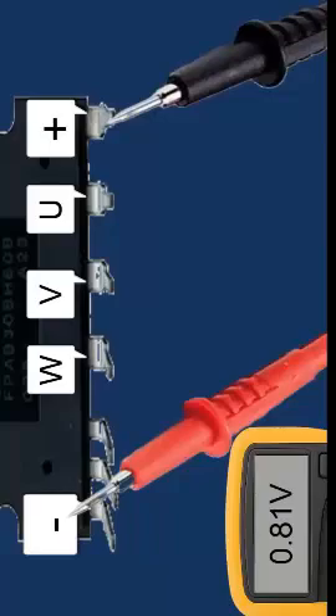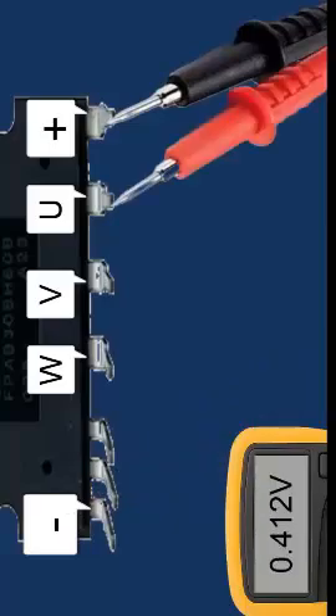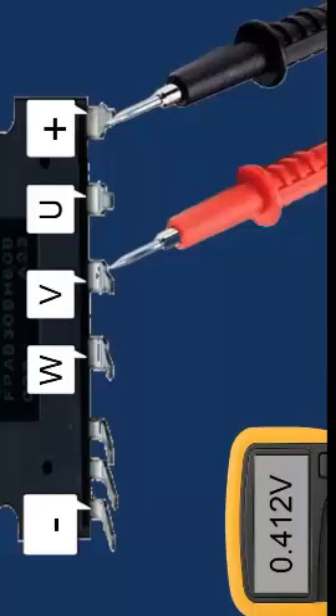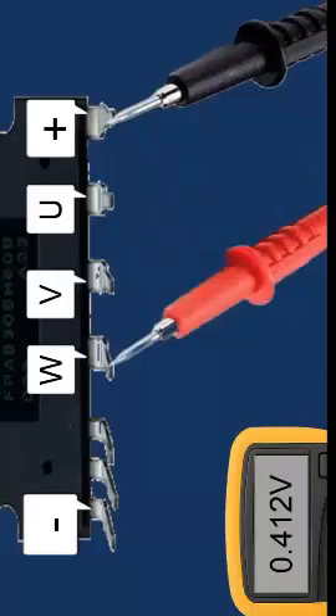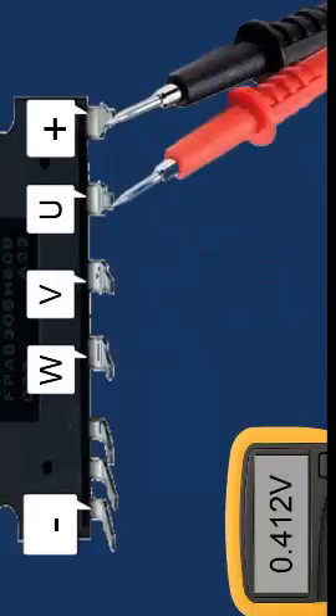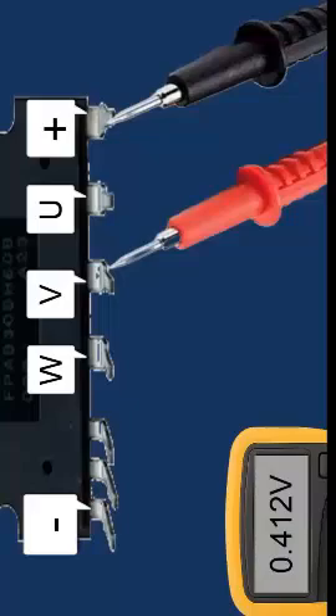Reverse the probe's polarity. Typical voltage drop should appear, around 0.813 volts between negative and positive. Keep the black probe fixed and test with the red probe on U, V, and W. All values obtained should be very similar.